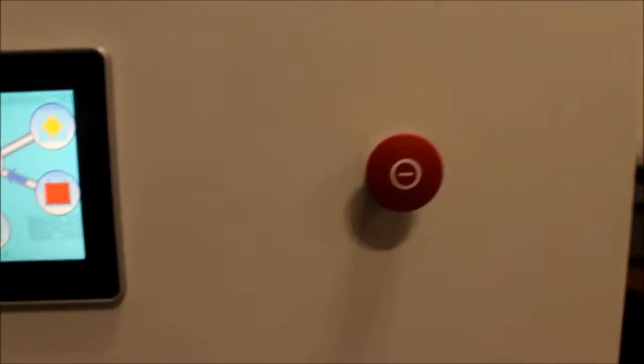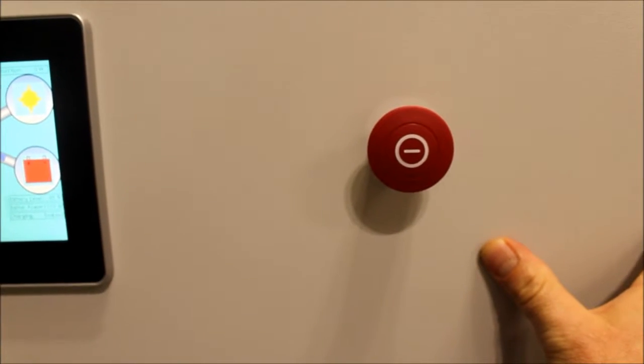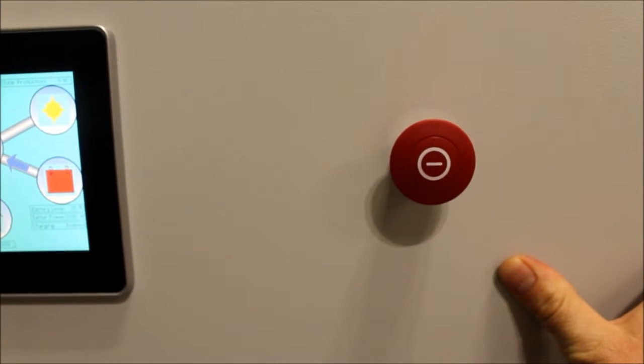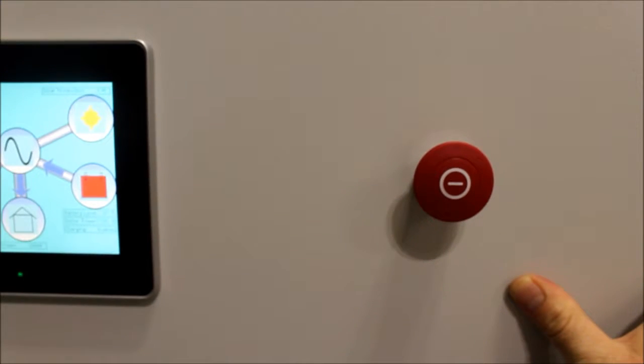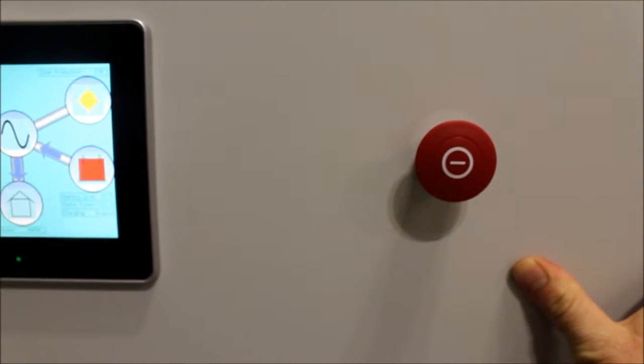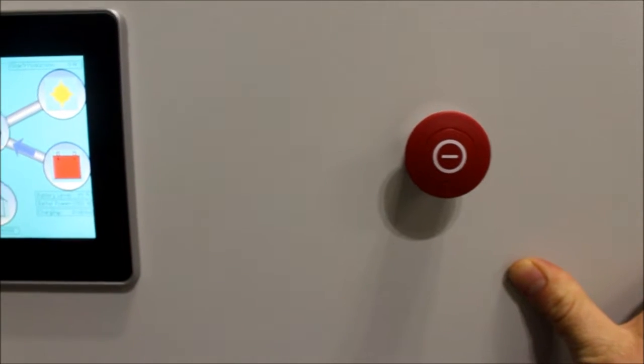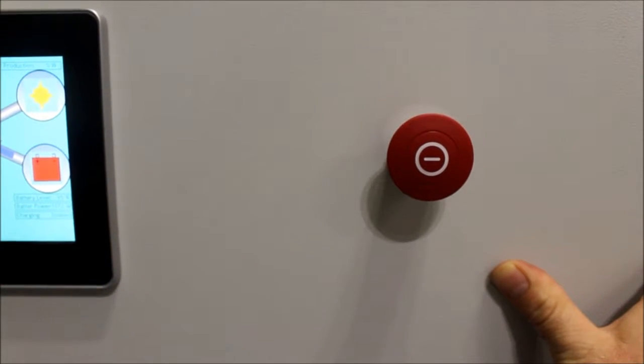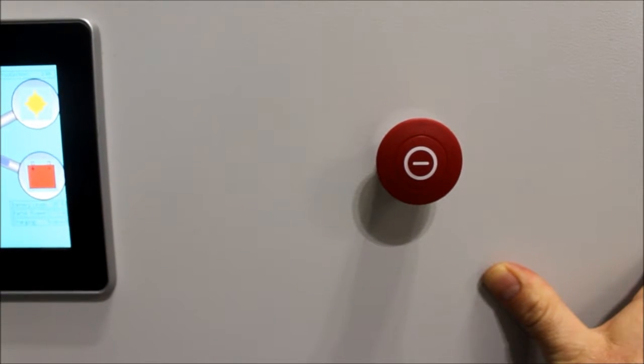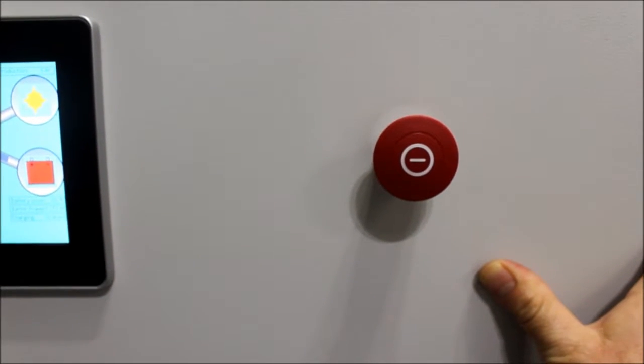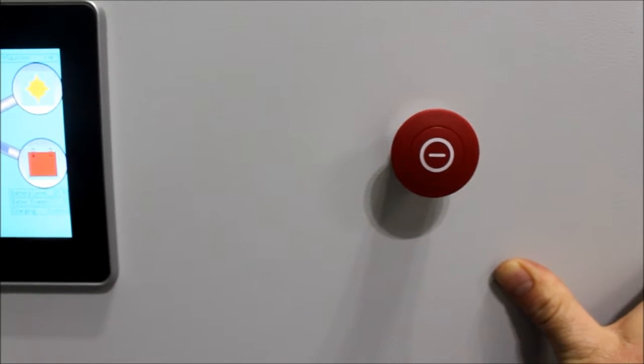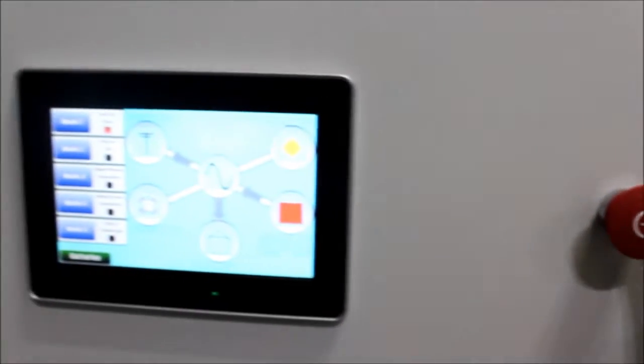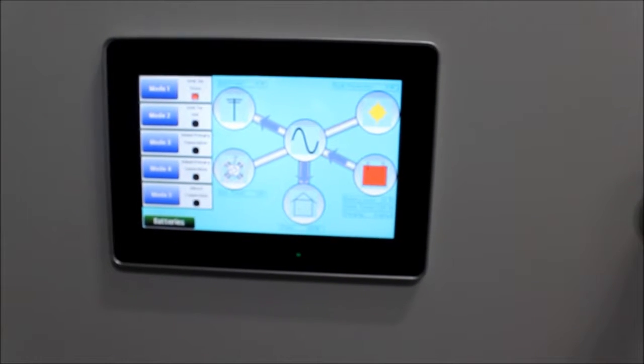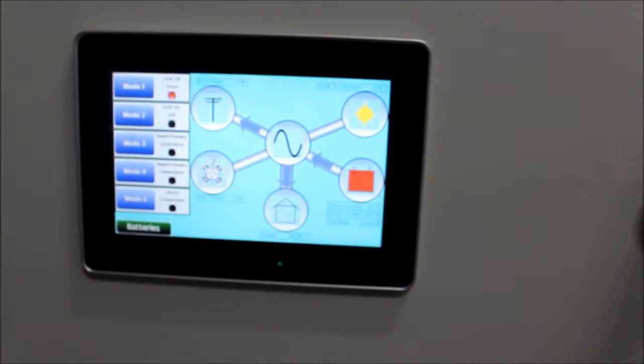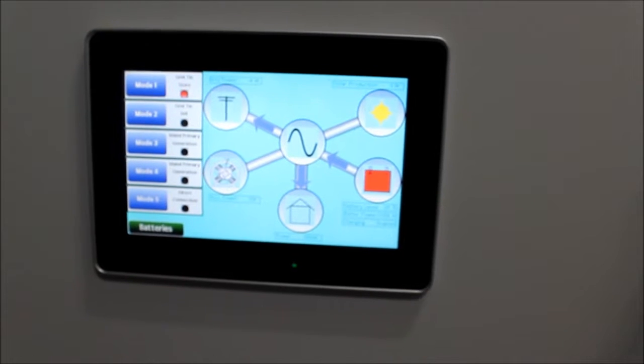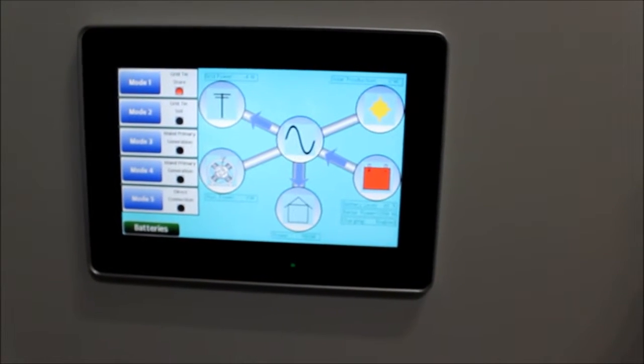The other way to set the mode 5 is through the manual override switch. And this is in the case of an equipment failure. This switch is wired such that it actually interrupts the power for all of the mode control relays, and they are wired so that with no power they default to mode 5. Additionally, it will cut power to the HMI display so that the homeowner is not confused about trying to operate the energy switch when it is in this bypassed mode.